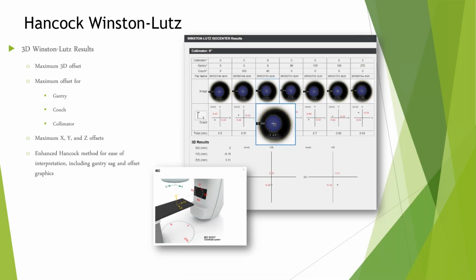Also included is the Winston-Lutz test for your stereotactic daily validation of your isocenter, including maximum 3D offset and individual offsets for gantry, couch, and collimator. There's also an enhanced Hancock method for ease of interpretation of the gantry sag and offset graphics.